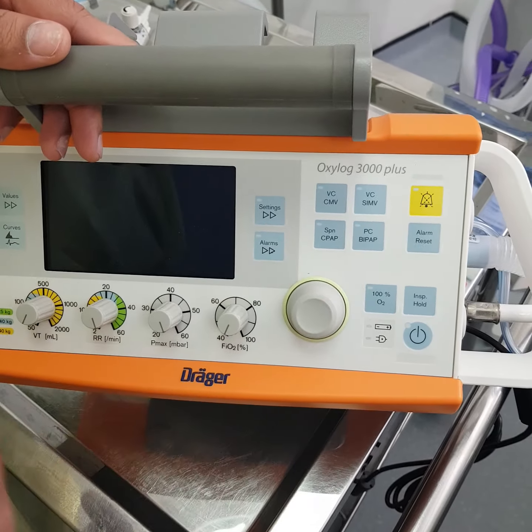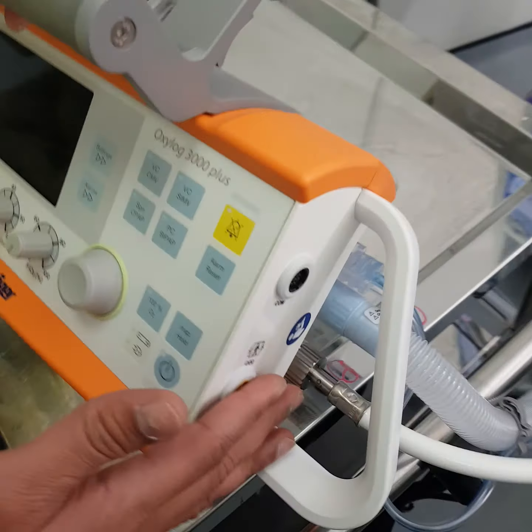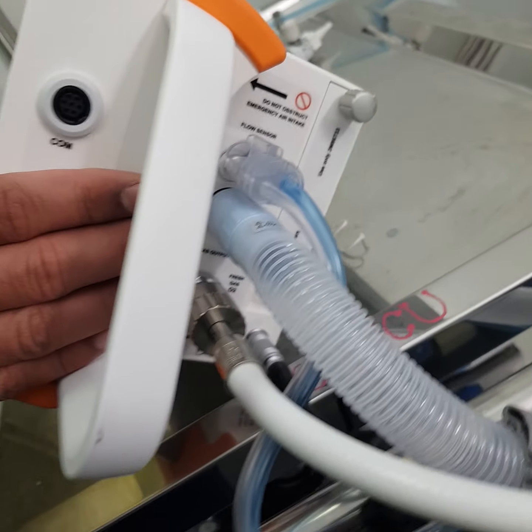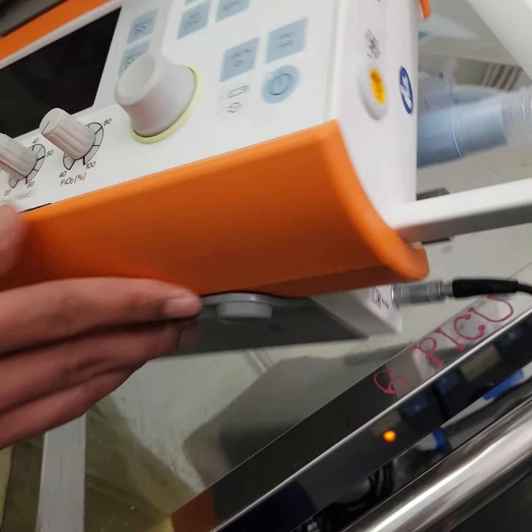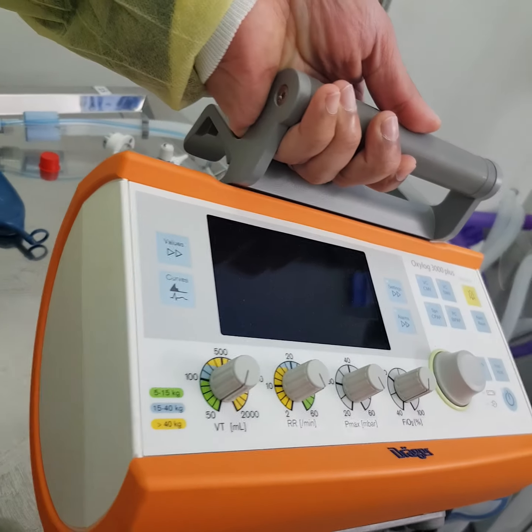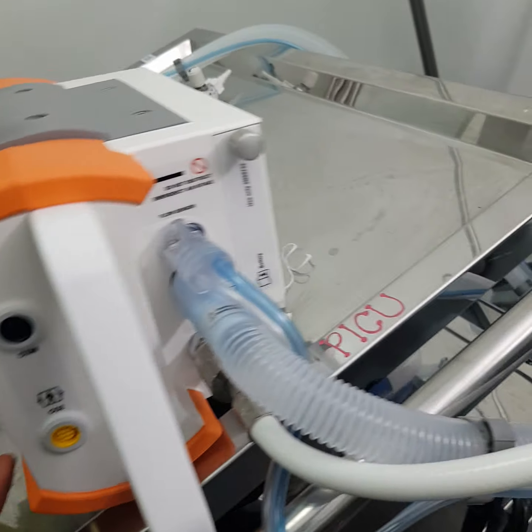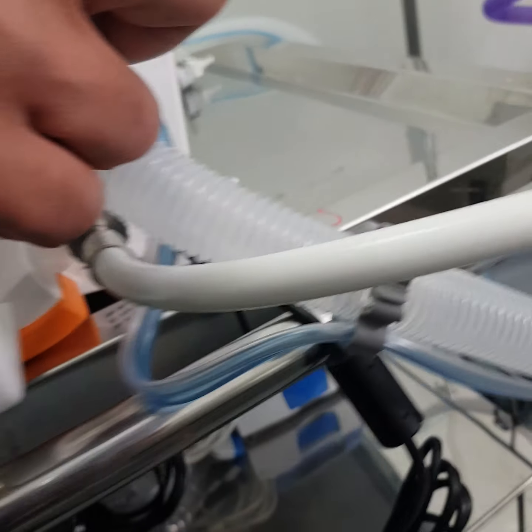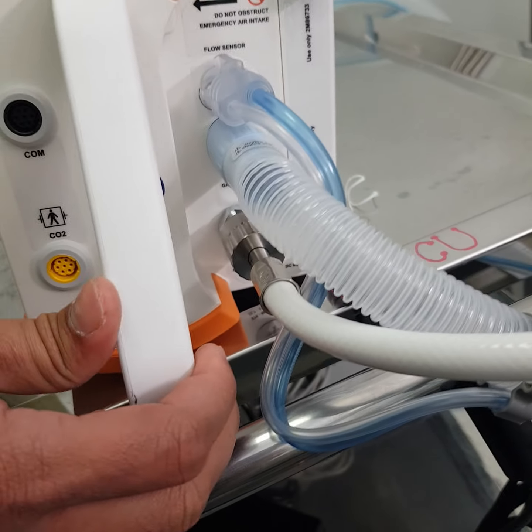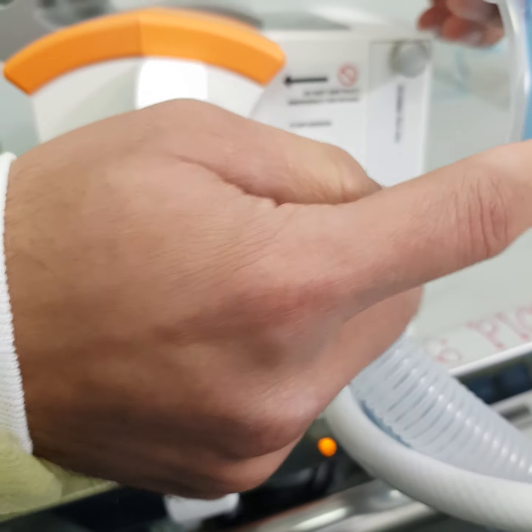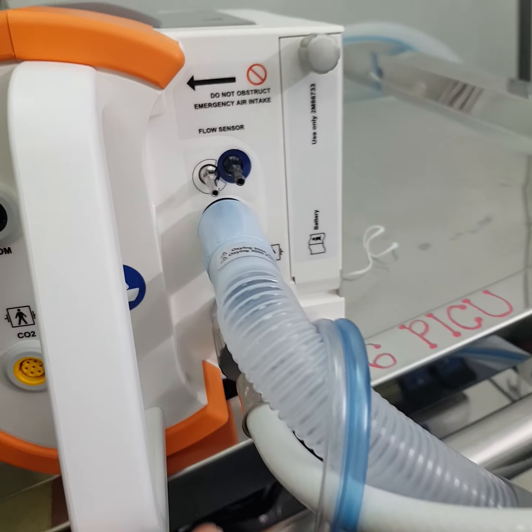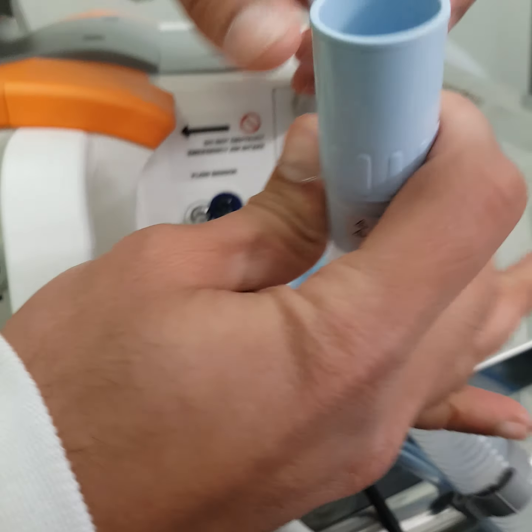And on the outer part of this ventilator, you have all the connections on this one side. So there will be no connections on the other side, as you can see. As with the older models, we are going to connect the ventilator circuit here. There are two smaller tubes, which are the flow sensor tubes, which have to be fitted into this blue and white port of the ventilator. And there is a bigger tube. So this is the ventilating tube circuit.